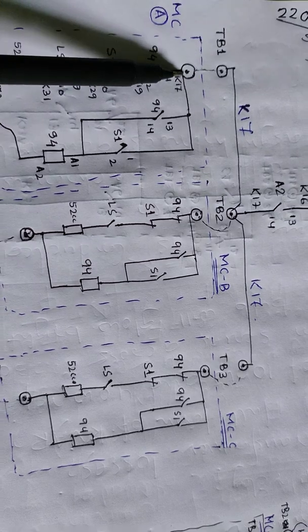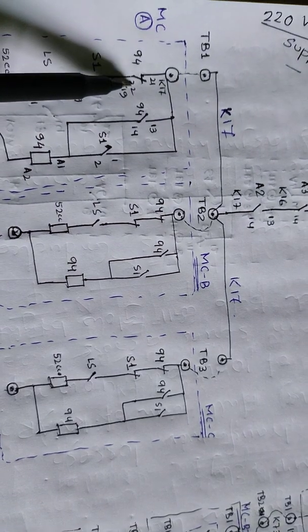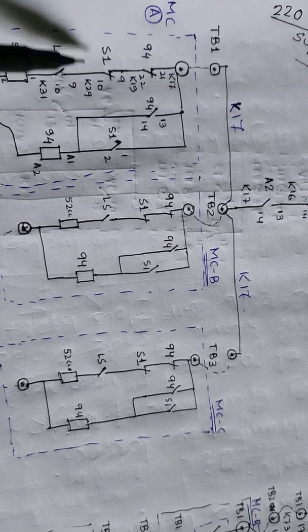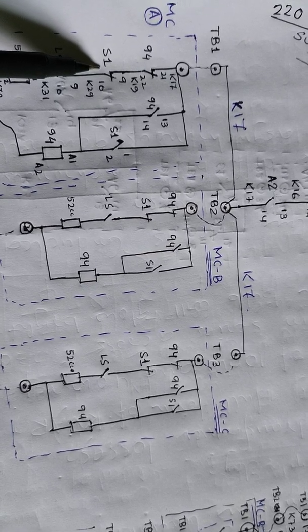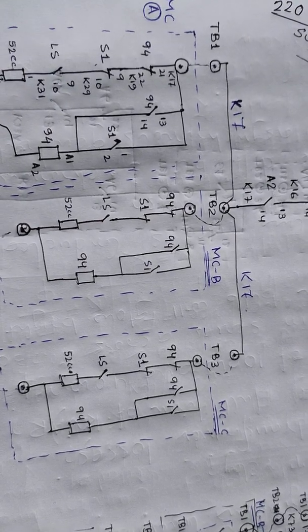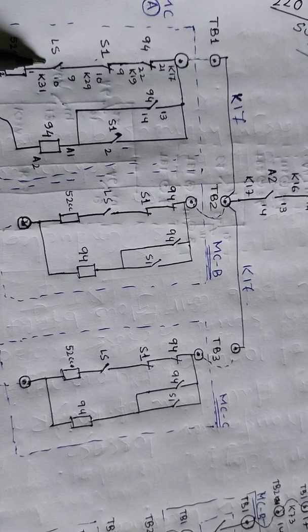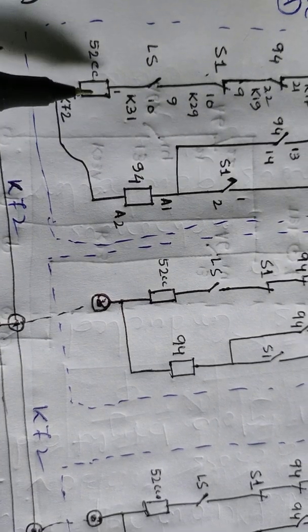The control circuit is accordingly for the red phase, Y phase and blue phase. This is the K17 contact, and the DC is coming from here. Contact 94 is the normally closed contact - this is the anti-pumping contact 21-22. S1 is the auxiliary contact of the breaker. If the breaker is in the off position, S1 is the NC contact. Contact 94 is NC, and LS is the spring mechanism. If the circuit breaker has a spring mechanism and the spring is charged, this contact is NC.